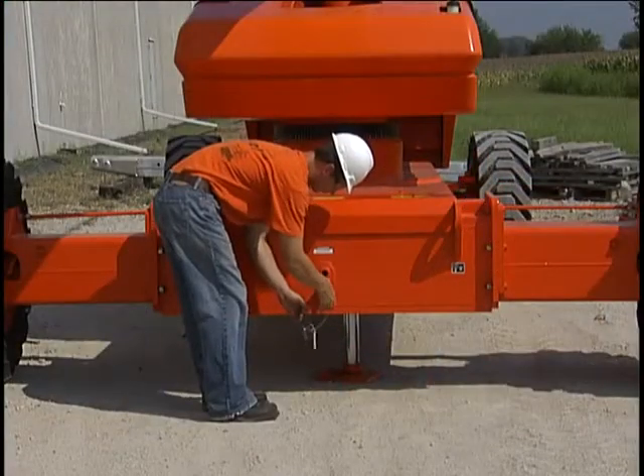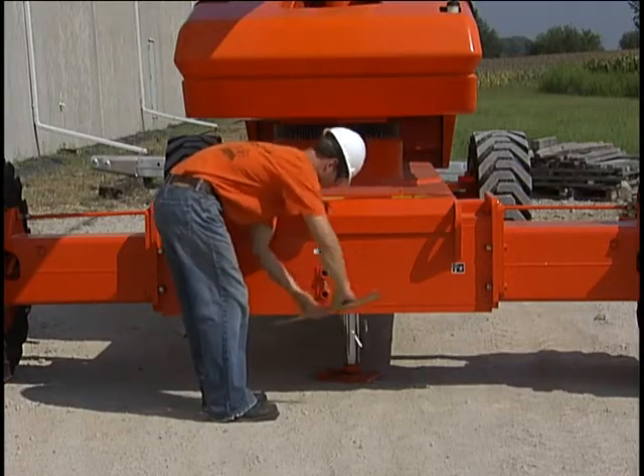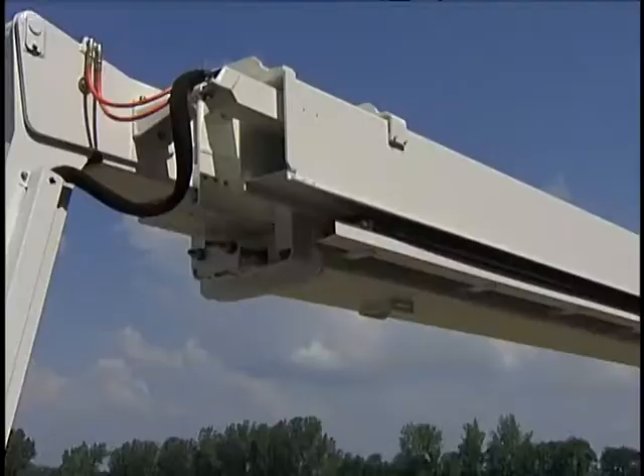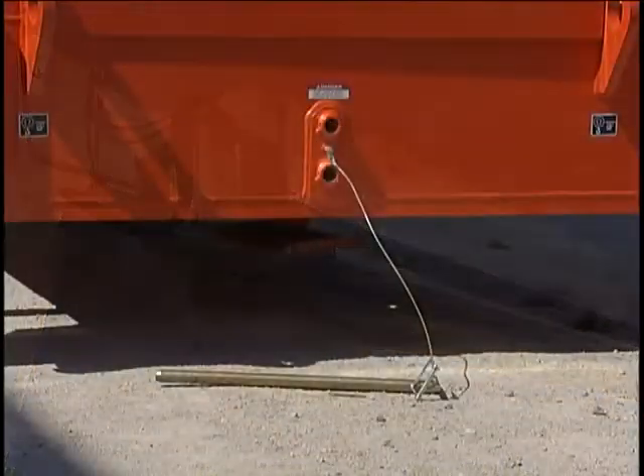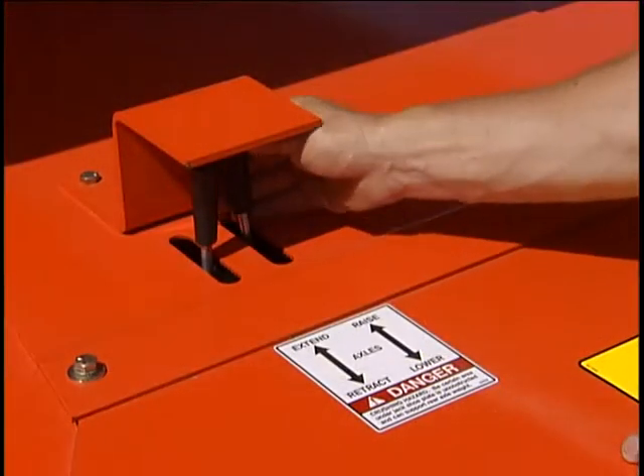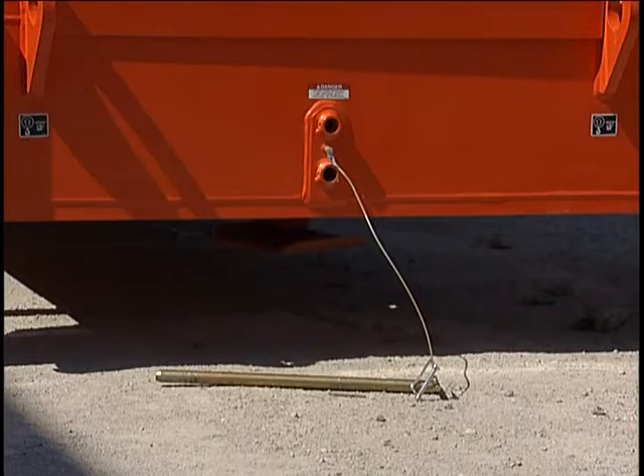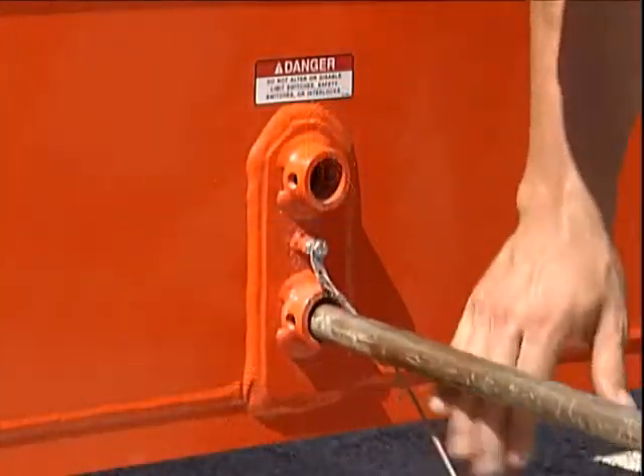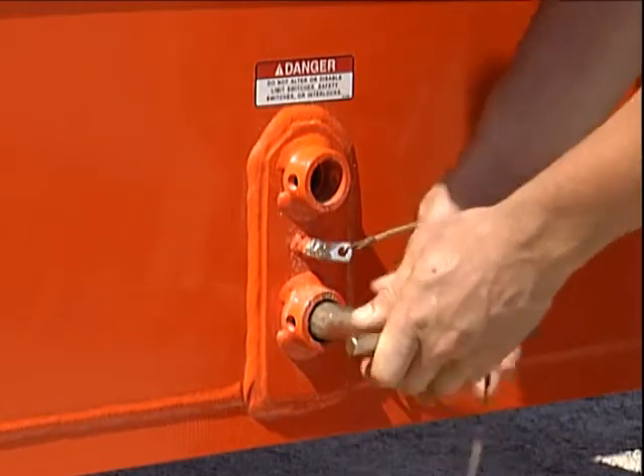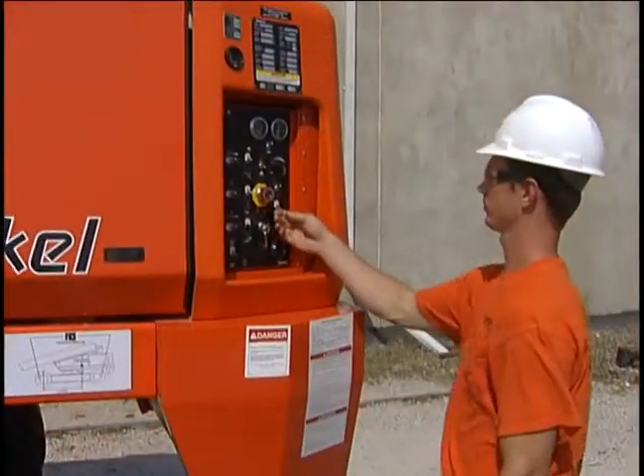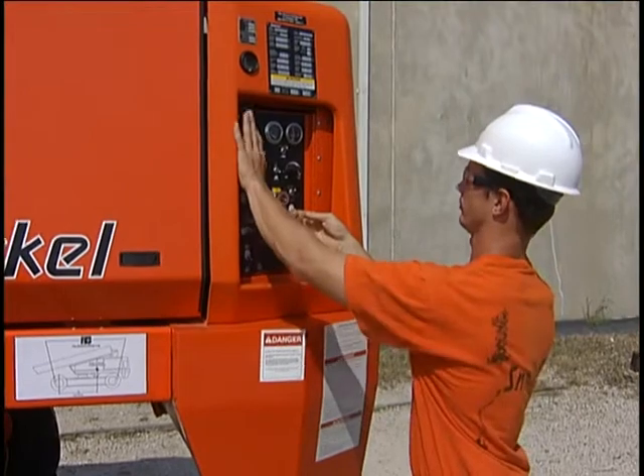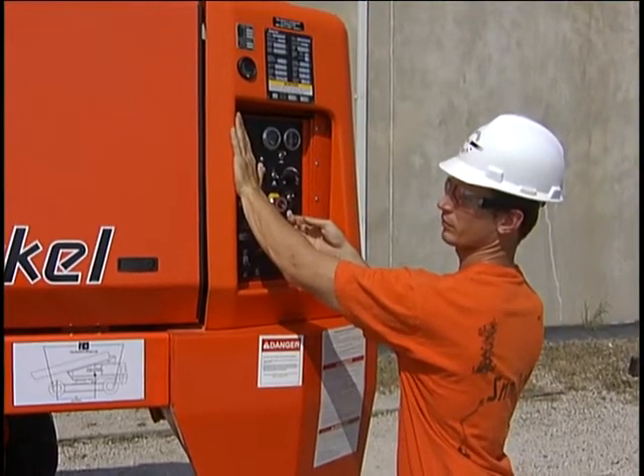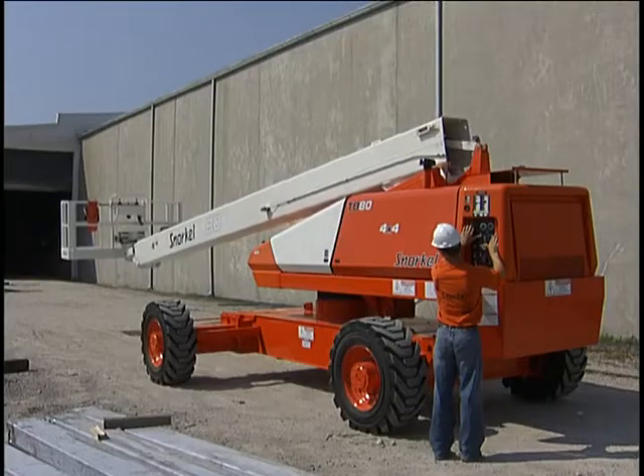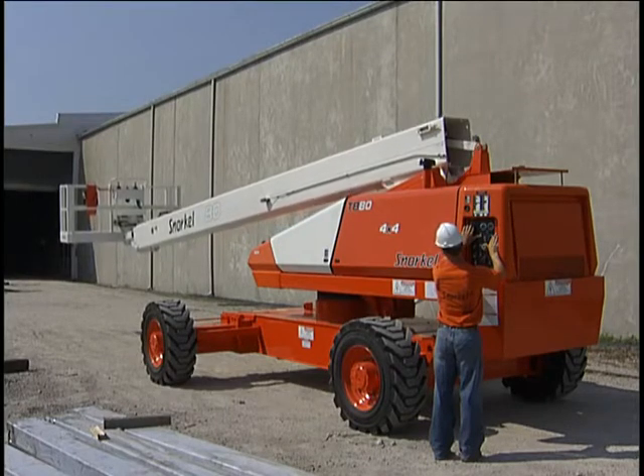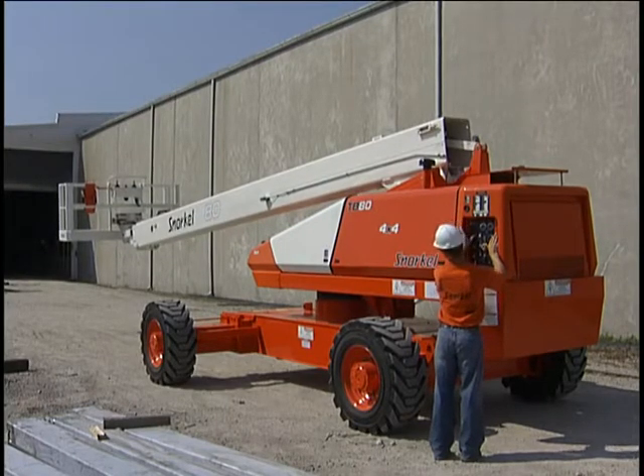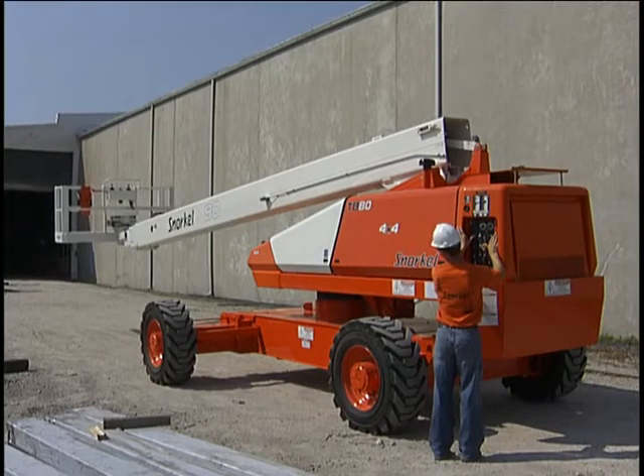Remove the pin again and attempt to operate the boom. The boom again should be capable of only slight movement. With the pin still out, try to operate the jack. The jack should not operate. Then, replace the pin and continue your inspection. At the lower control panel, with the lower controls selected, hold the ground operation switch up and operate the controls to make sure each function works in both directions. We'll demonstrate these controls in the next section of this video.